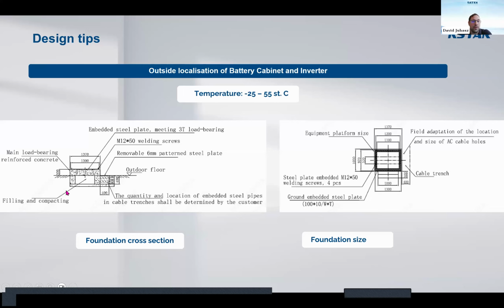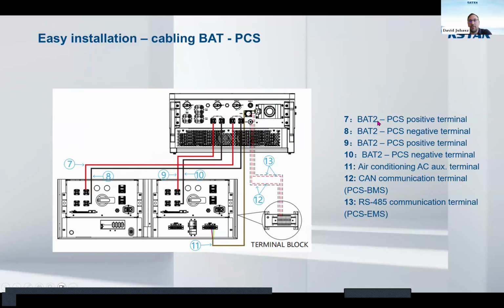There are the drawings for the foundation. It needs to be made from concrete, and the cross-section and also the foundation cross-section, the size are drawn and can be downloaded. Okay, so the schematics clearly show where to connect which communication port or which DC connection cable, and here we can see that the BMS and the PCS have the CAN communication protocol, and the EMS and the PCS have the RS485 protocol.